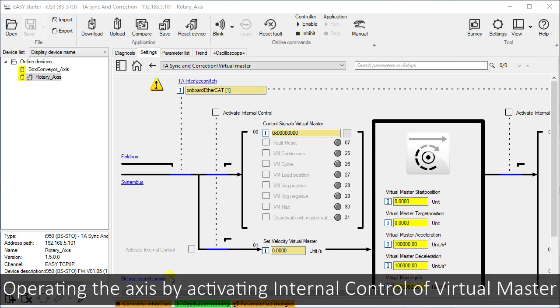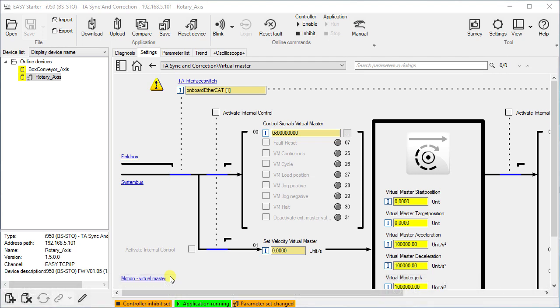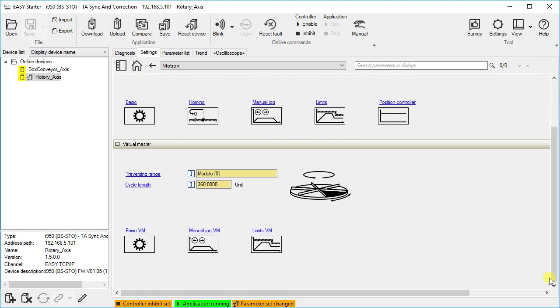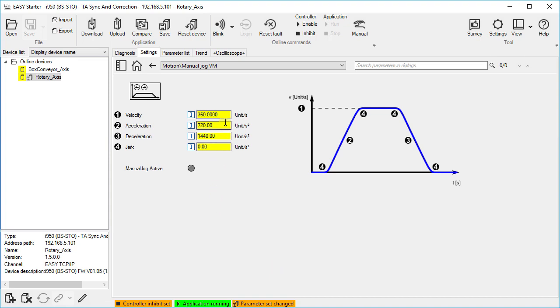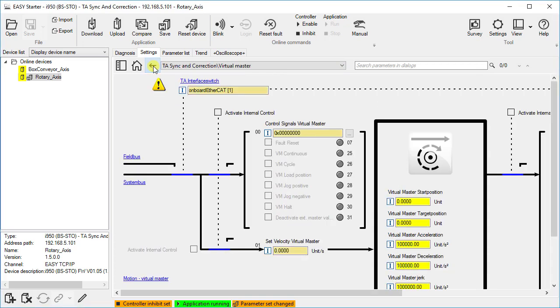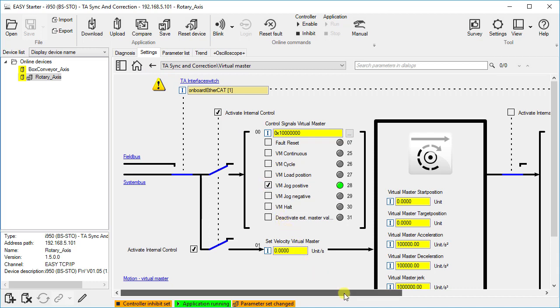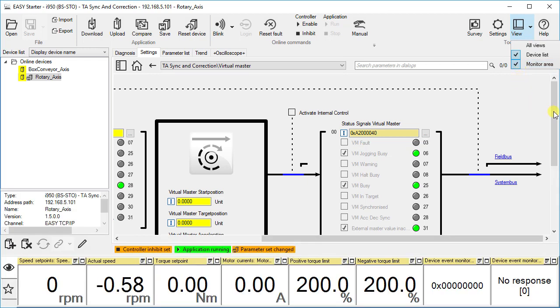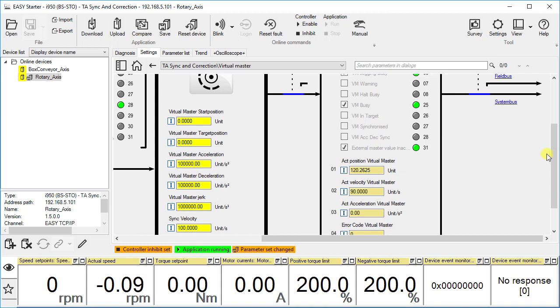Now let us jog the virtual axis by internal control. To set jog velocity, click on to motion virtual master, then click on manual jog VM. We will reduce the velocity to 90 units per second and keep the other parameters. Go back to the virtual master interface and activate internal control. Check the box of jog positive. Here you can see the actual position and actual velocity of the virtual drive. To verify the movement, we drag and drop the actual VM position into the monitor area.